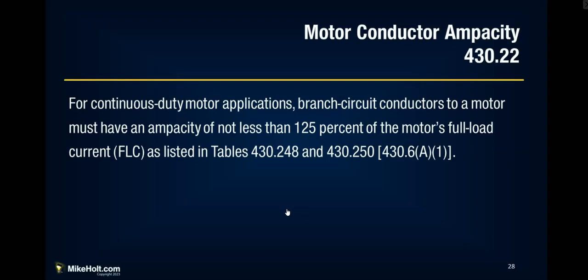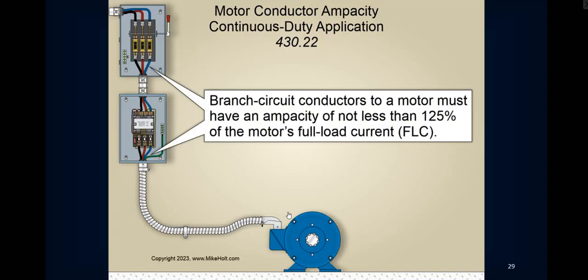So conductor ampacity. For continuous duty motor applications, branch circuit conductors to a motor must have an ampacity of not less than 125% of the motor's full load current as listed in tables 430.248 and 430.250. Those tables are giving you the ampacity which is specified for those motors. It's not from the nameplate. So branch circuit conductors, this is 430.22: branch circuit conductors to a motor must have an ampacity of not less than 125% of the motor's FLC.